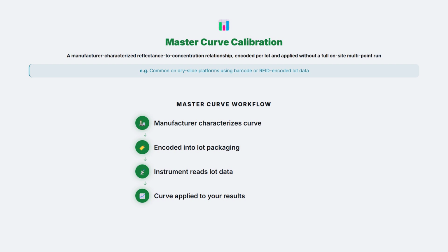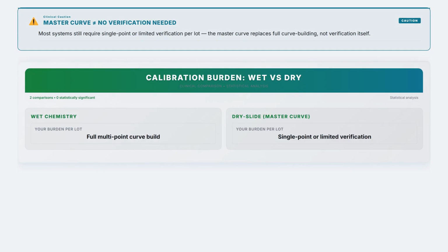This doesn't mean you're off the hook for calibration entirely. It shifts the burden from full curve building to single-point verification. Most systems still require running one or more calibrator or control materials at the start of each new lot, confirming that this specific lot's master curve is actually tracking correctly on this specific instrument before releasing patient results.